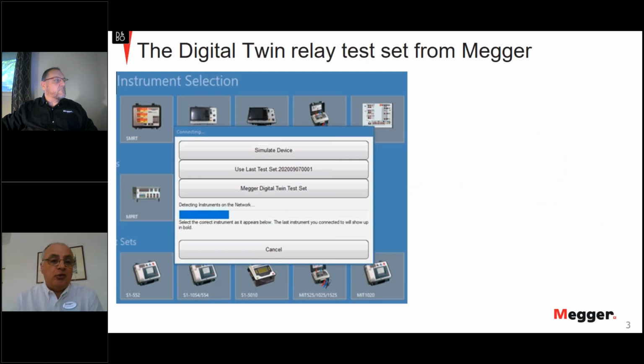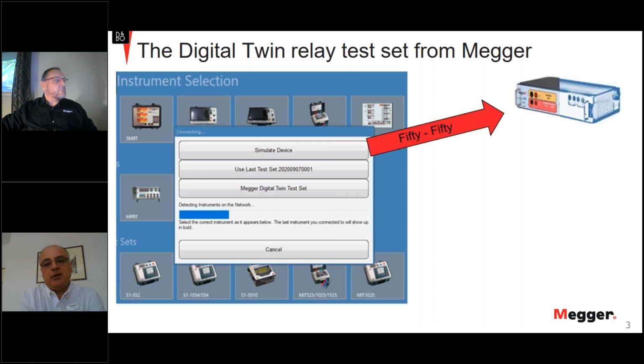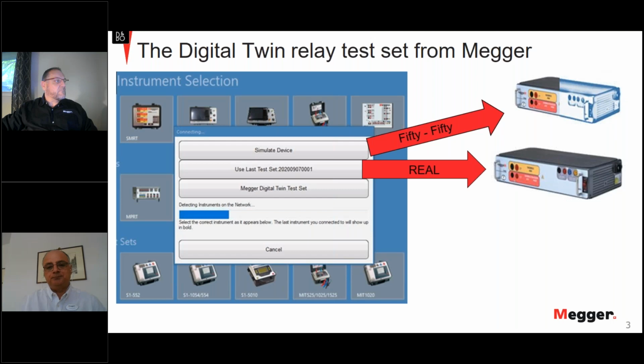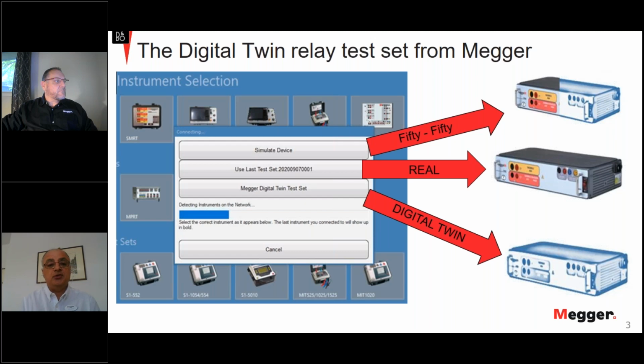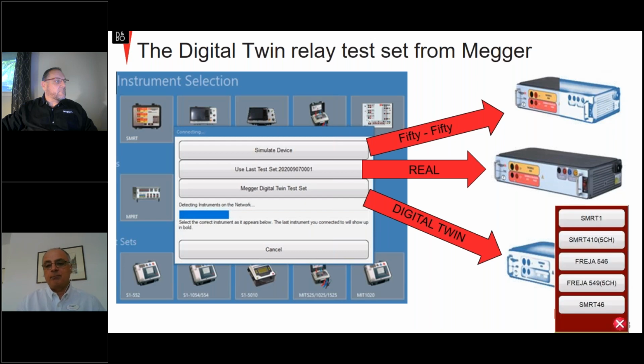So in RTMS software, when we connect, it's asking us to connect to the real test set, we can eventually simulate the device, which is something between 50-50 between a real relay and the simulation world. It's not this I want to talk about. We can connect it to a real test set, or now we can connect to a digital twin. It's a replica inside the computer, a full replica of the test set, and there is a full dialogue between the software and the digital twin. And here you have the relays we can choose under digital twin mode.